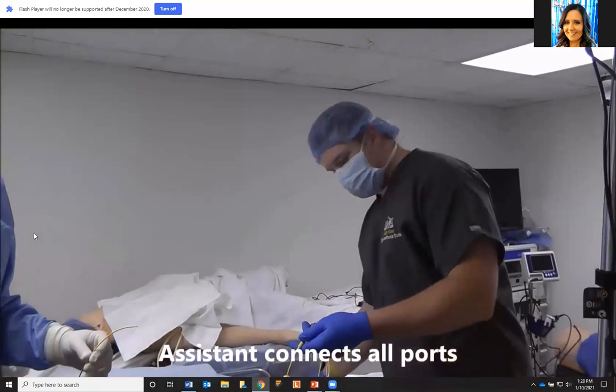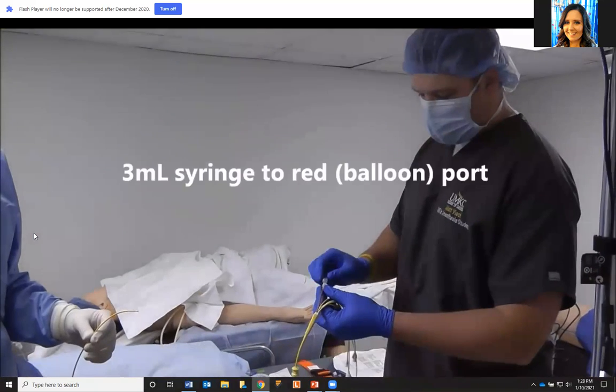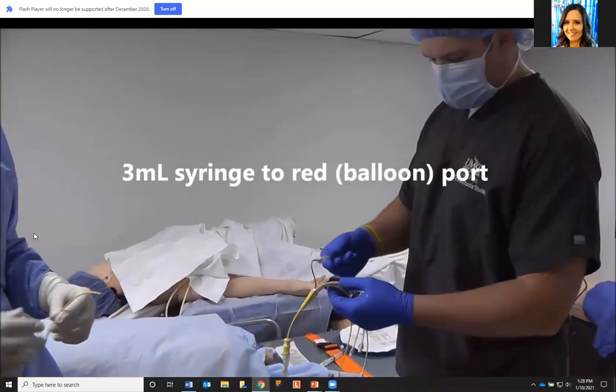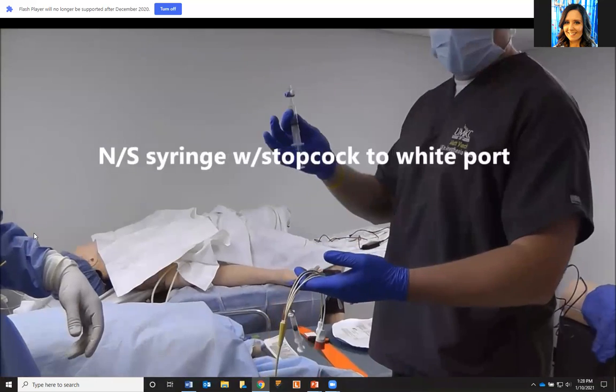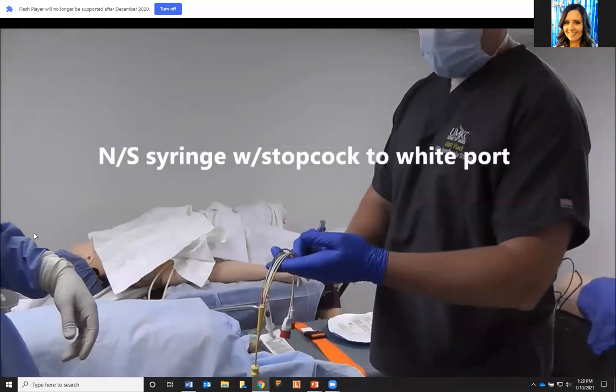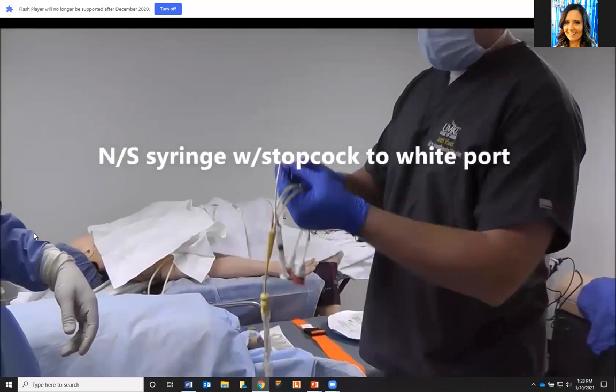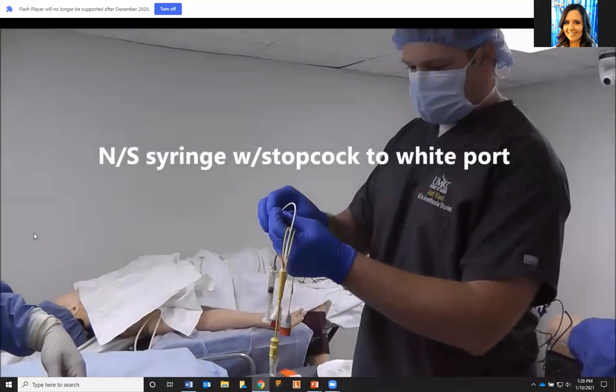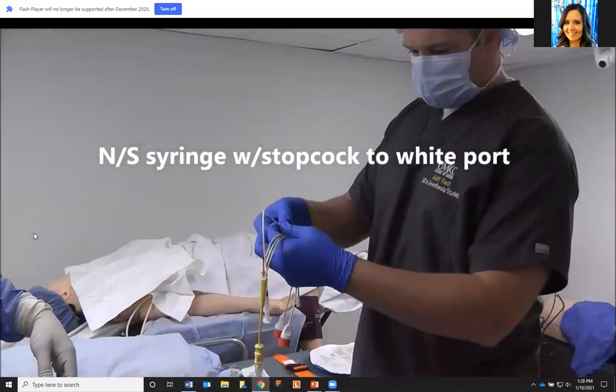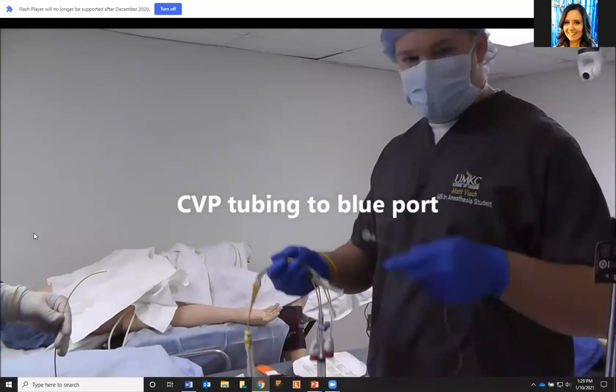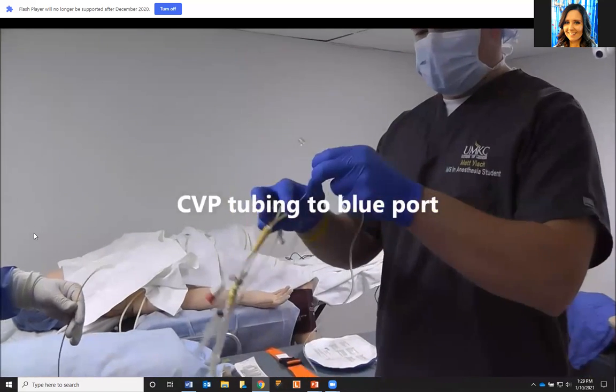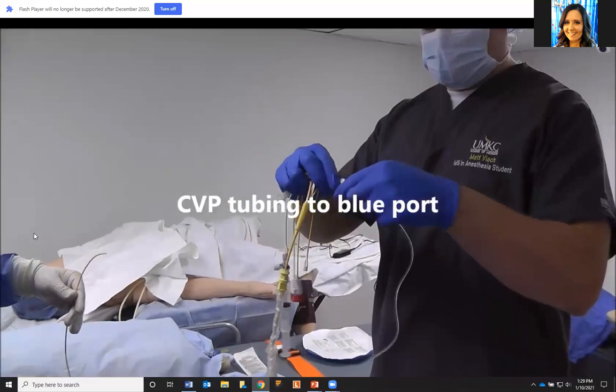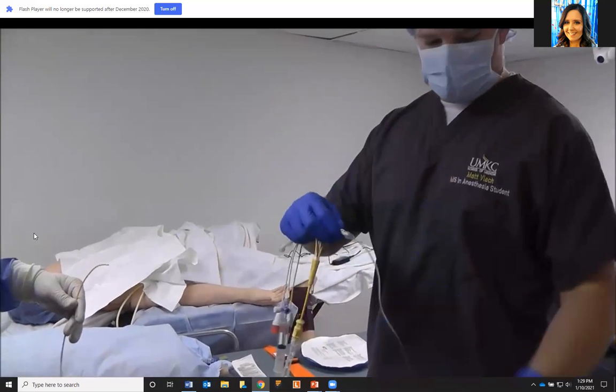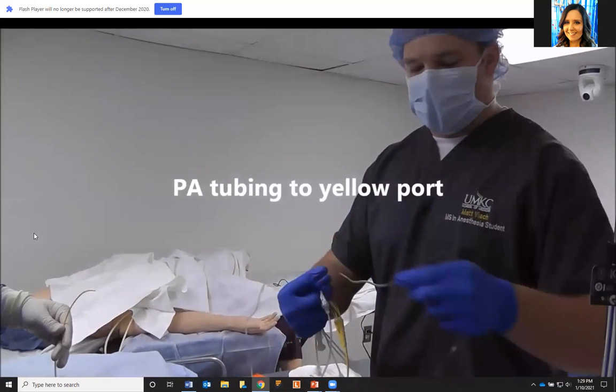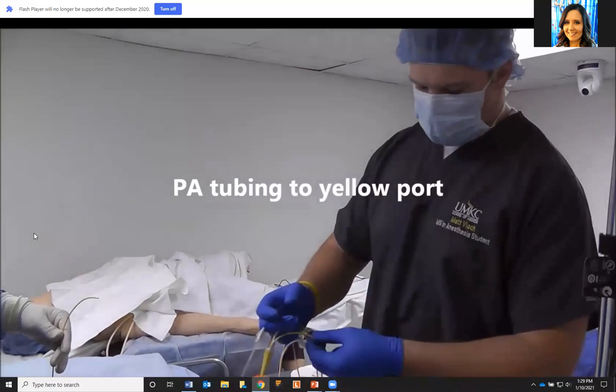All right, so I'm going to hook up this syringe to the balloon port, the red port right here. Now I'm going to hook up this saline to the white port. Now I'm going to hook up my CVP tubing to the blue port. And then I'm going to hook up my PA tubing to this yellow port here.